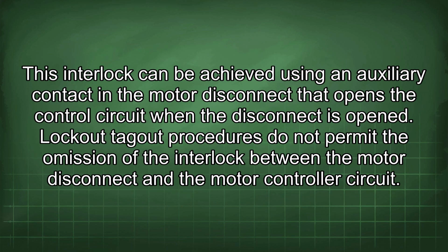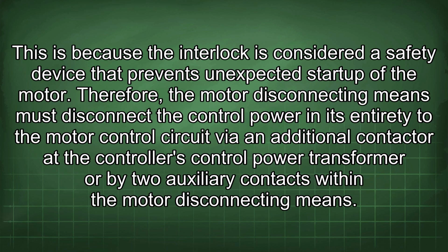This interlock can be achieved using an auxiliary contact in the motor disconnect that opens the control circuit when the disconnect is opened. Lockout-tagout procedures do not permit the omission of the interlock between the motor disconnect and the motor controller circuit. This is because the interlock is considered a safety device that prevents unexpected startup of the motor. Therefore, the motor disconnecting means must disconnect the control power in its entirety to the motor control circuit via an additional contactor at the controller's control power transformer or by two auxiliary contacts within the motor disconnecting means.